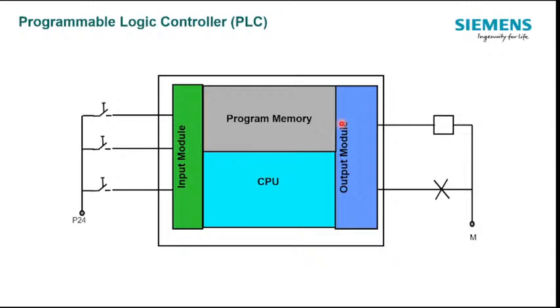So I will connect my start push button over here, so that when I am not pressing the start push button, this positive 24 volt will be available up to this point. As soon as I press the start push button, the circuit will be closed and this positive 24 volt will be applied to the input terminal here. Each input terminal and each output terminal will have a dedicated assigned memory address.